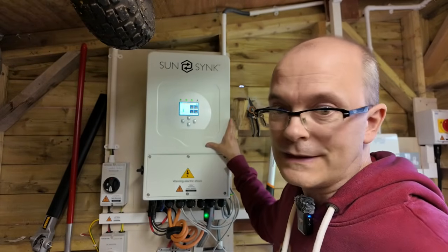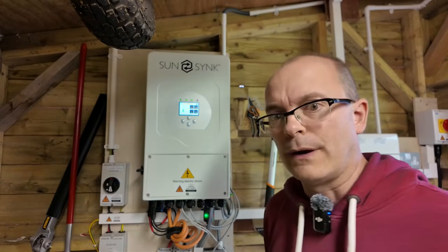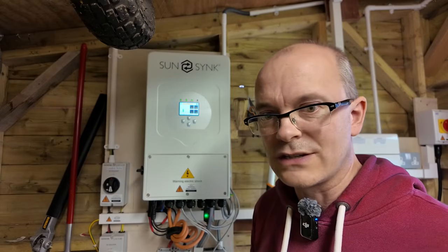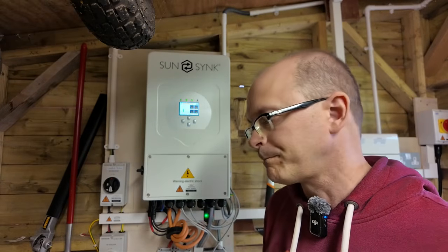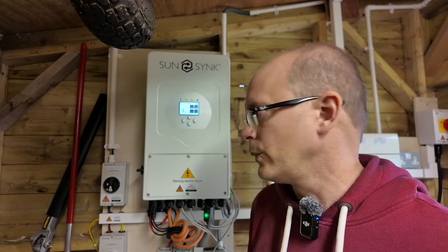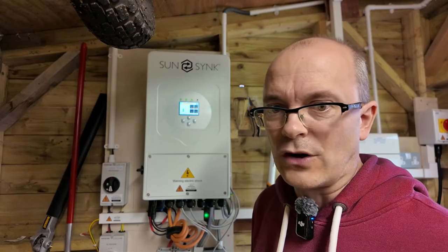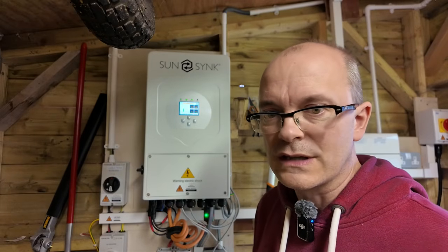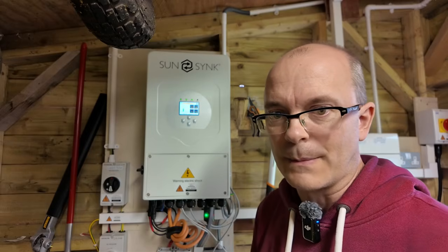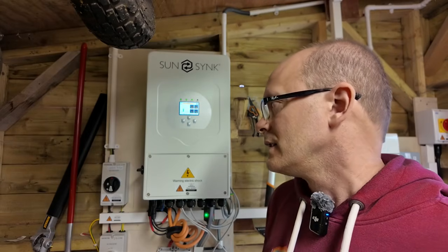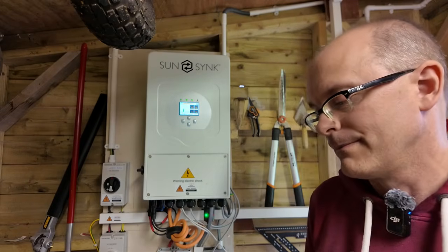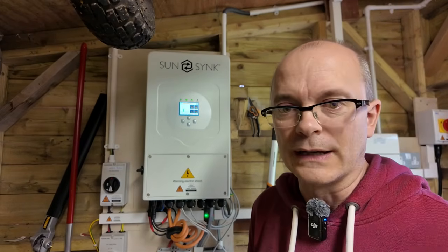Now, at the moment it's set to 15%, the low battery state, but I'm thinking of increasing that to 51%, so that when we discharge the battery down to 50% in the evening time, it will just simply switch the inverter off. And then when the solar power comes back on again in the morning time, it will switch the inverter back on once it gets above the battery restart level. I think I can control those things using Modbus. In the wintertime, it becomes more tricky.